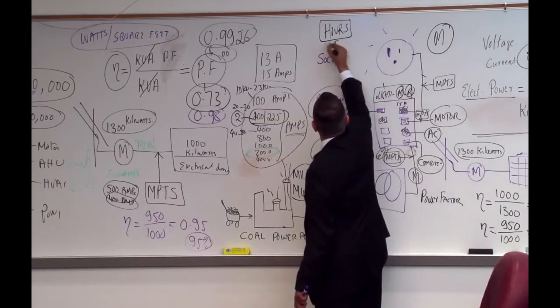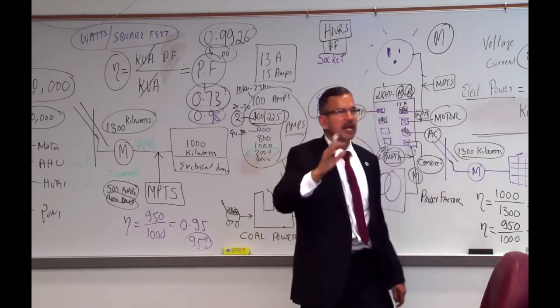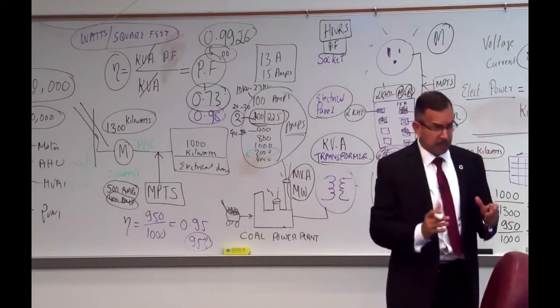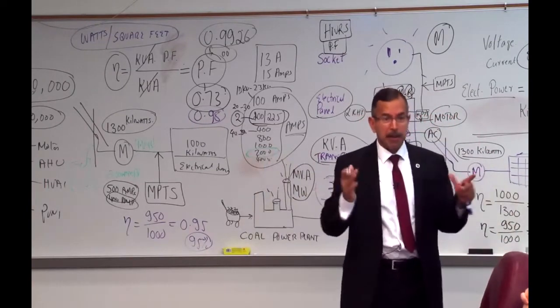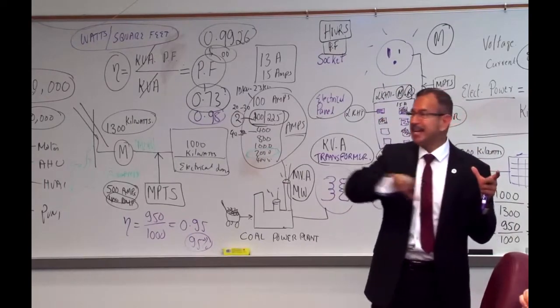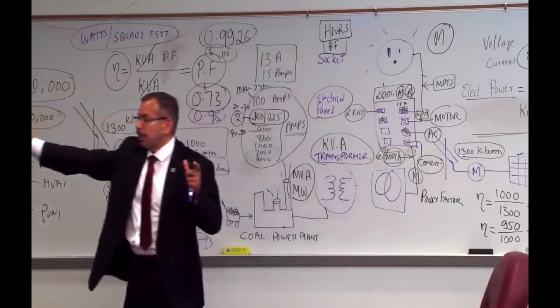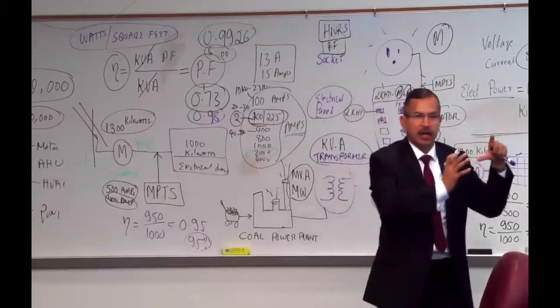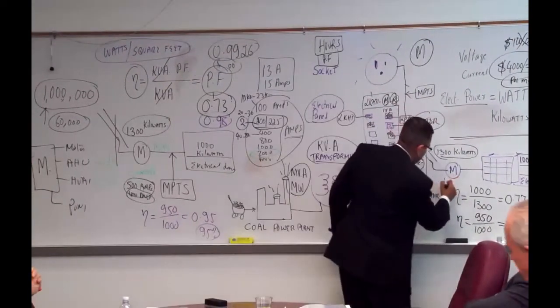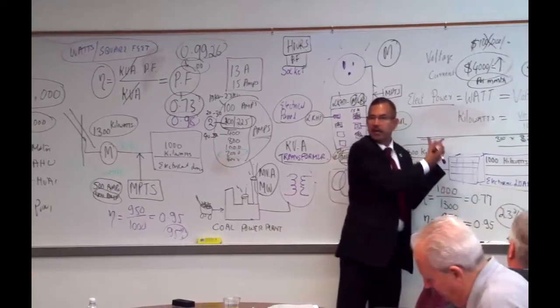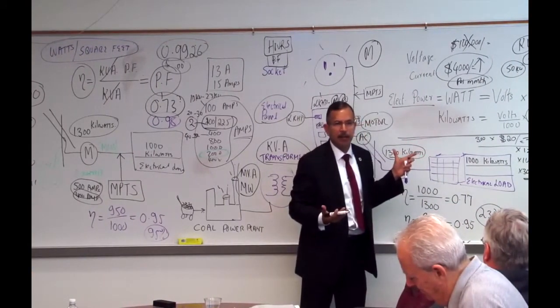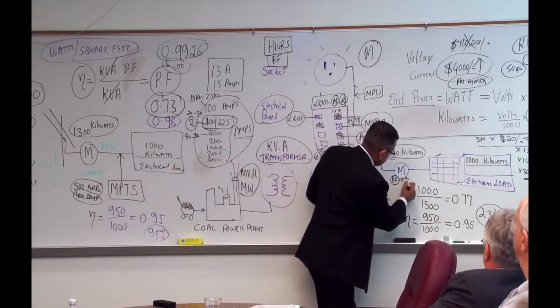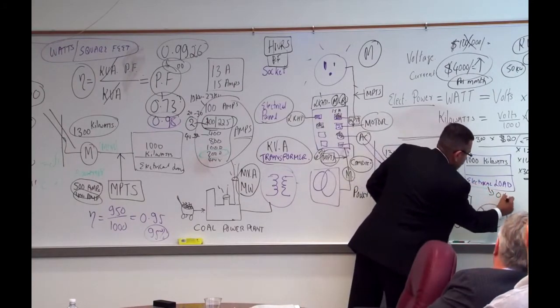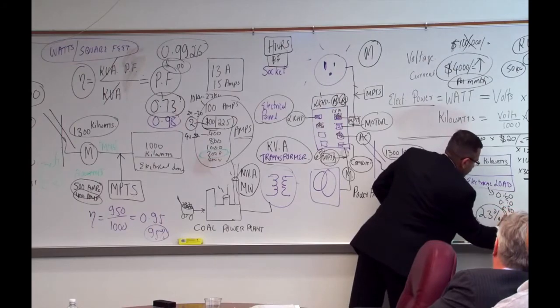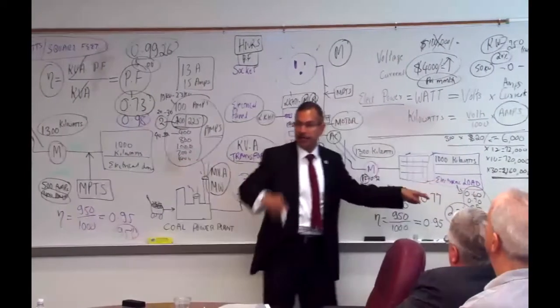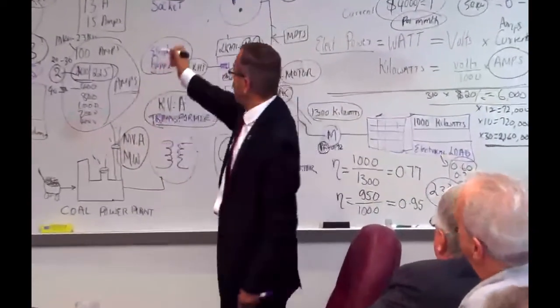The second factor is the power factor of the inefficient load. Don't get misled by 'my building is LEED certified, Energy Star' - those buildings are where we save the most energy because they're above 90%. When you go inside that LEED certified building, you have air conditioners. Your building power factor is an average value at the meter - it's the average of all resistive, inductive, and capacitive loads. It's an average number, but within that average of 0.92, you have equipment running at 0.60, 0.70, 0.80, 0.85 power factor. So as was said, we'll only target those loads - the second criteria is to pick the inefficient load.